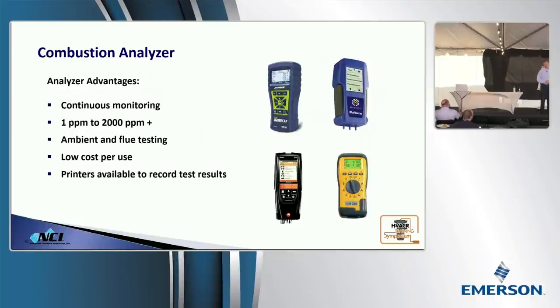But believe you me, though, we charge for it. We had to, because there are maintenance fees that go along with this. Every 2 years, you can bank on it, you're going to replace an oxygen sensor. They go bad. Carbon monoxide sensors are a little bit more durable. But there will be maintenance issues. If you want to self-destruct the oxygen sensor, leave the hoses attached. They'll go bad in a year, sometimes 6 months.